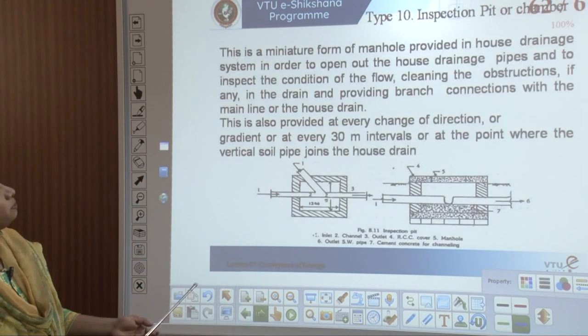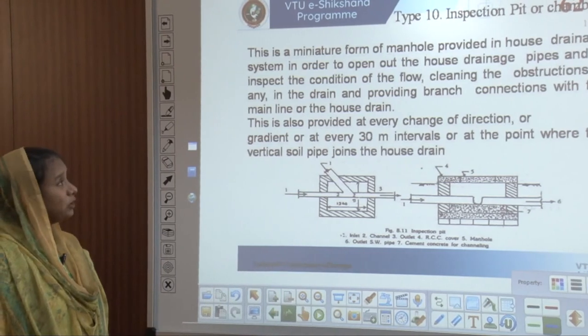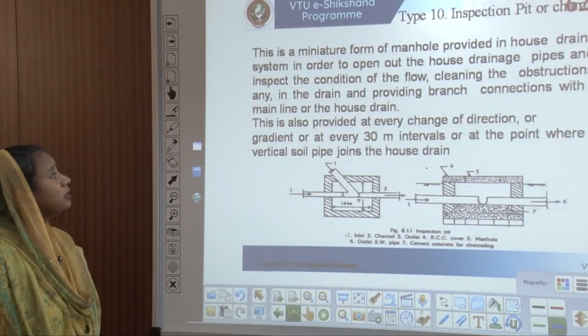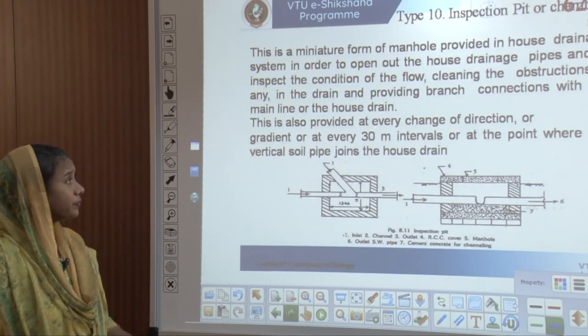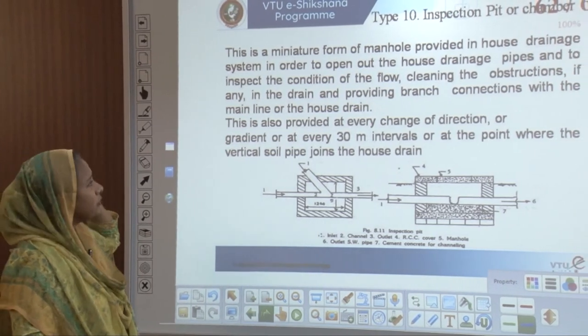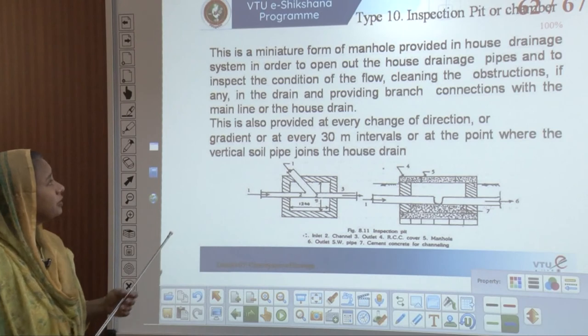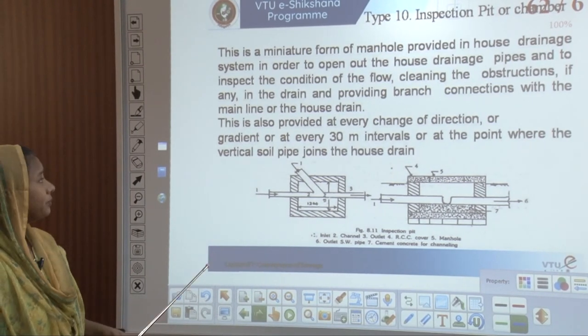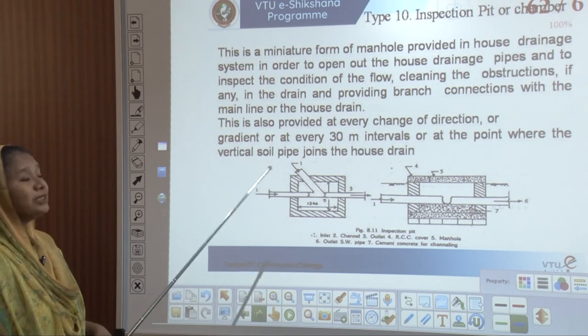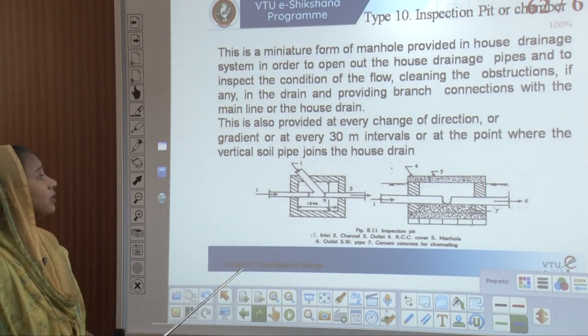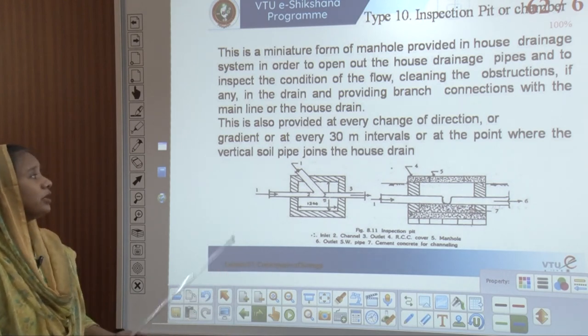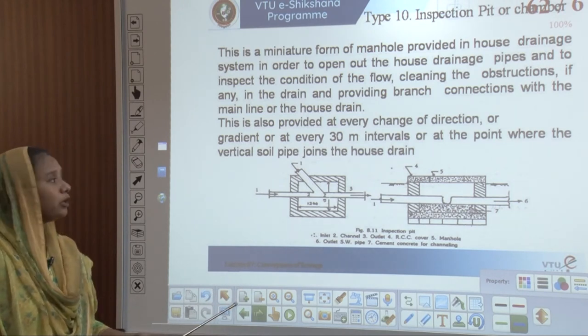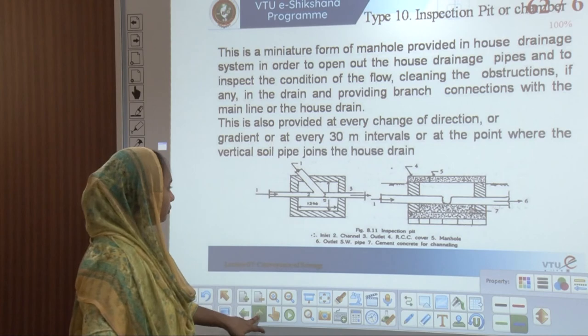An inspection pit or chamber is a miniature form of a manhole provided in each house drainage system to open out the house drainage, inspect the condition of flow, clean obstructions, and provide branch connections with the main line or house drain. It is also provided at every change of direction, change of gradient, or every 30 meters interval at the point where vertical soil pipes join the house drain.